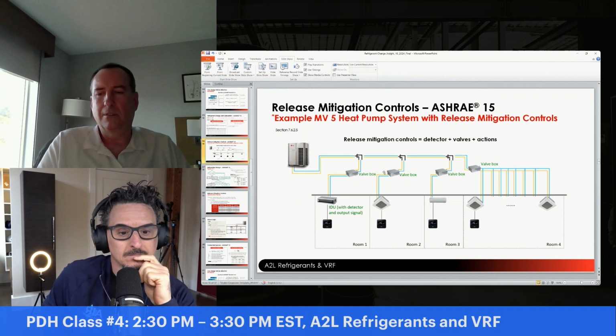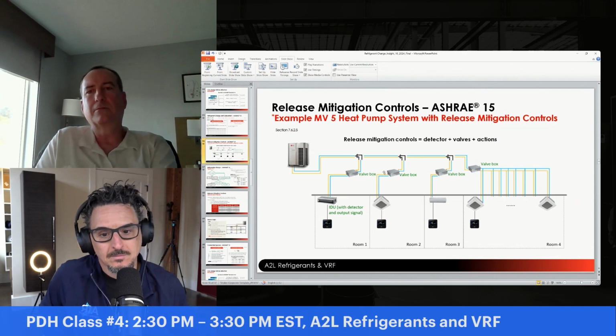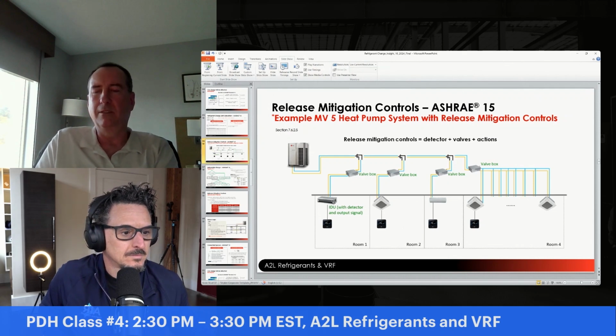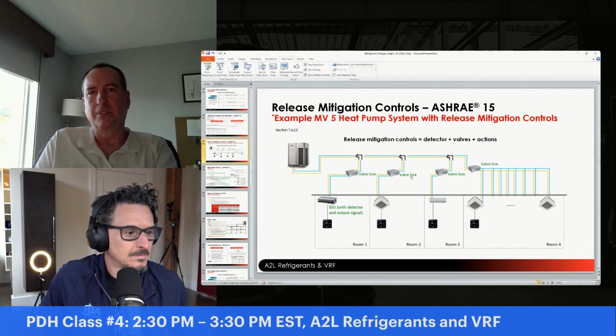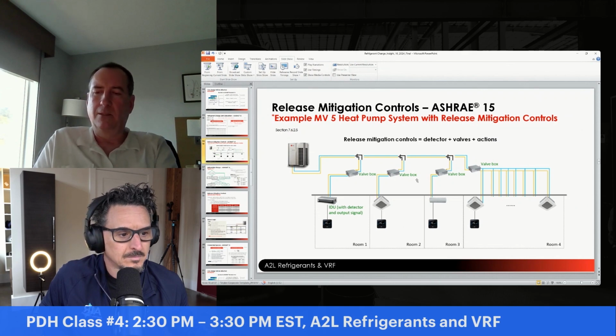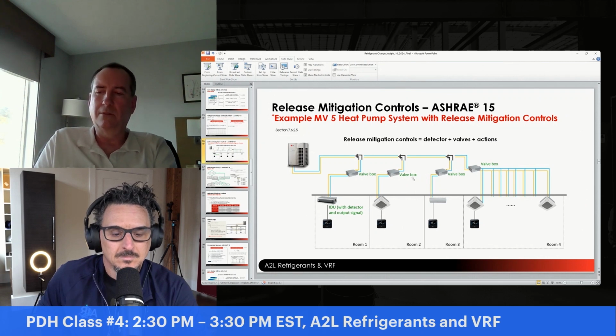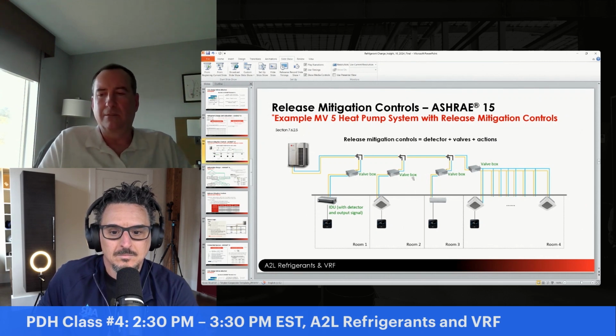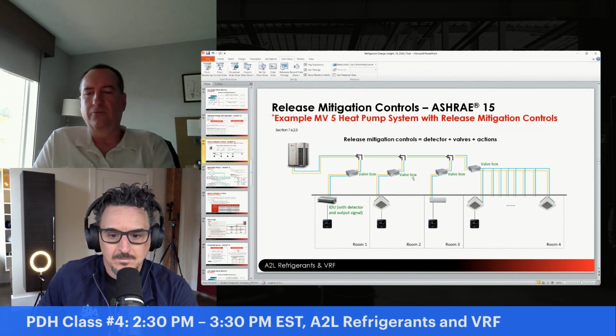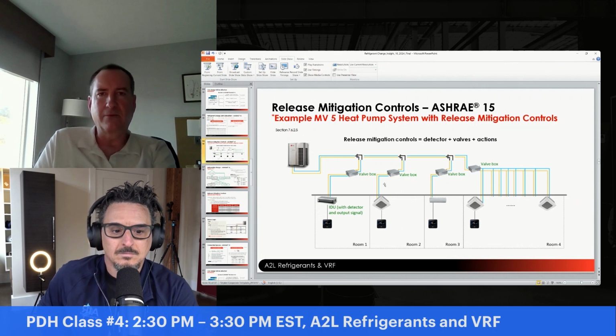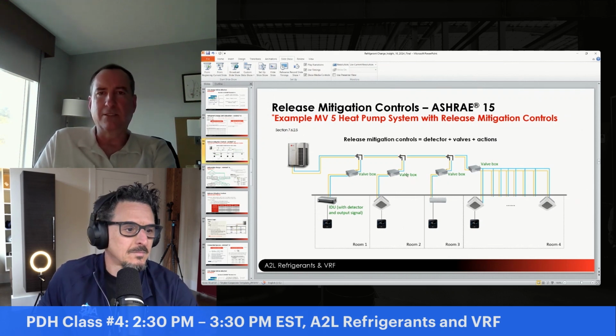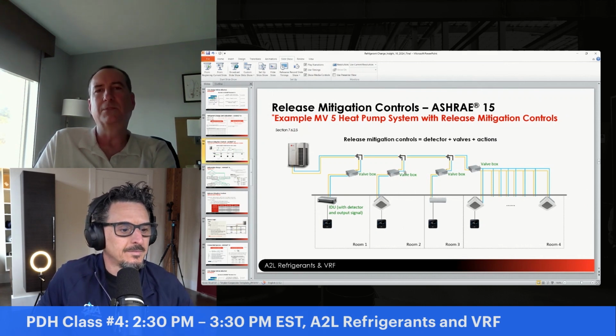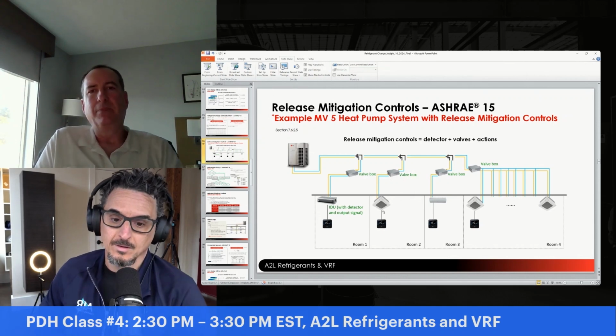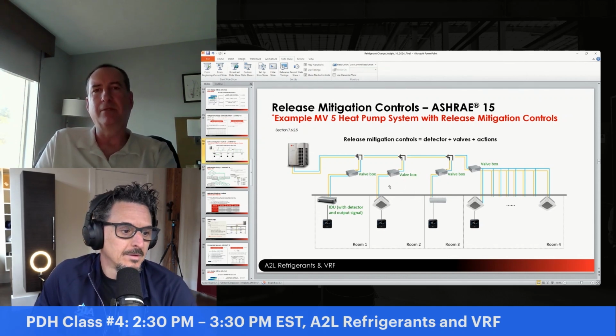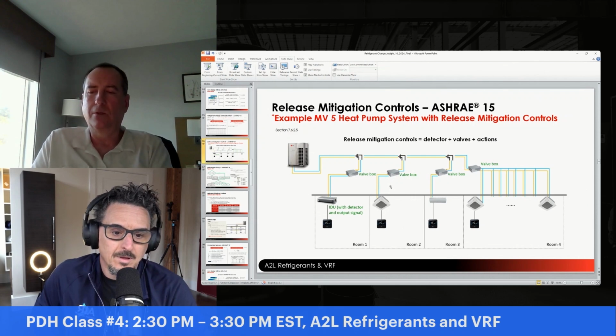So what these controls include are integrated refrigerant leak sensors, leak detectors, and I'll talk some more about that, but they're going to be included in all of the indoor units. It also is going to include these shutoff valves that you see, where it's labeled valve box. And then when this particular mitigation system is used, the possible quantity that could be leaked into the room is limited to the volume of refrigerant that passes through the valve during detection and closing of the valves, plus whatever charge you've got downstream. So that is what you have to deal with rather than the entire charge of the whole system. Because you can shut this refrigerant pipe off and isolate everything here. So that's kind of how we're going about it.